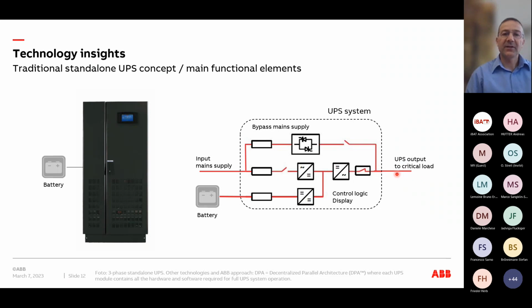In this picture you see a so-called double conversion concept, where the power always flows first through the UPS system to serve the end customer. In case of a power trip, the battery is connected directly, so the load doesn't even realize the power grid has tripped. Then there's a bypass for maintenance. This is a concept used a lot.